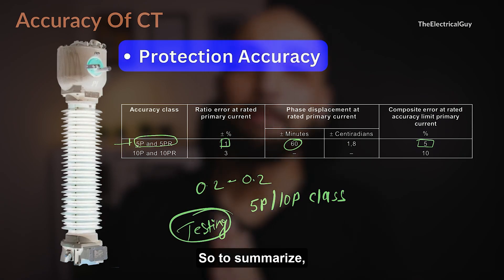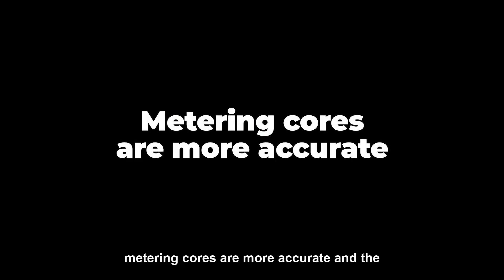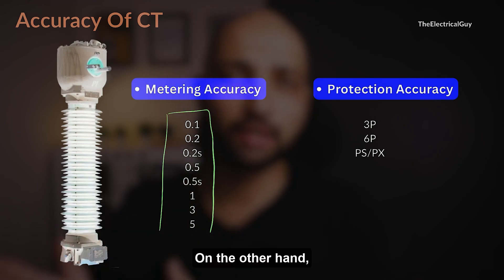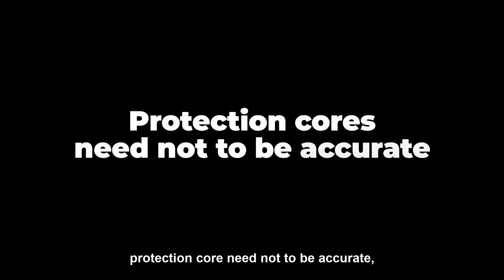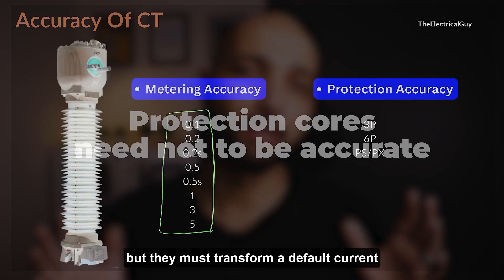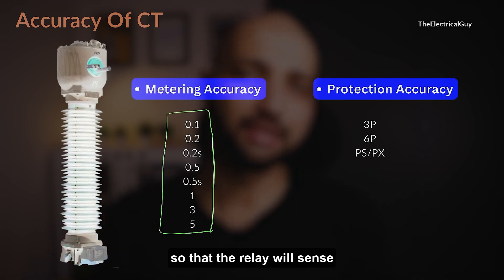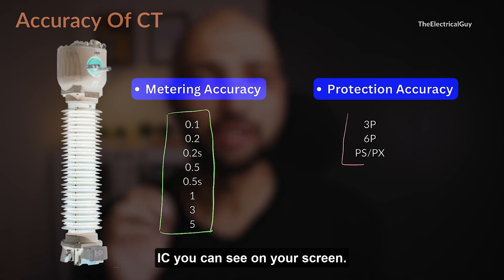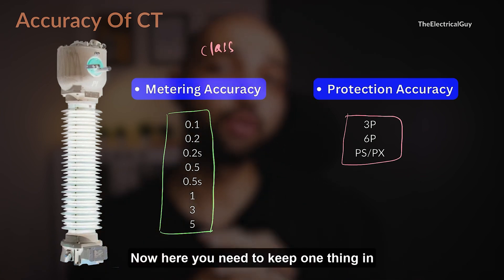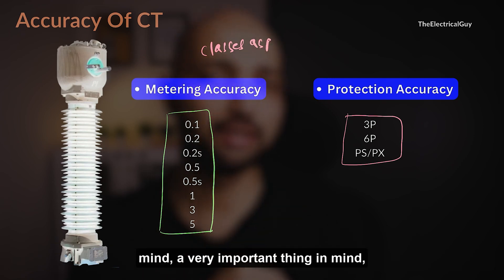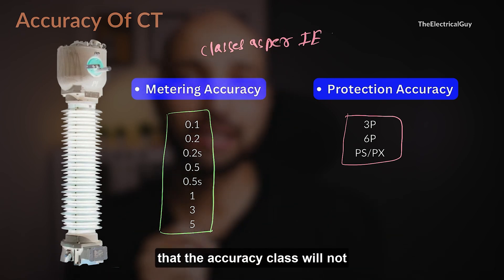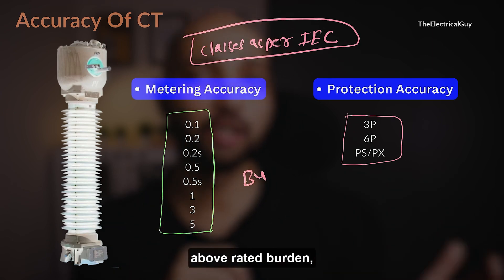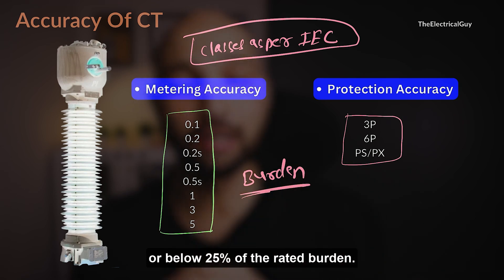To summarize: metering cores are more accurate, with classes defined by IEC standards. On the other hand, protection cores need not be as accurate, but they must transform fault current so that the relay will sense it and clear the fault. One important thing to keep in mind is that the accuracy class will not be guaranteed for burdens above the rated burden or below 25% of the rated burden.